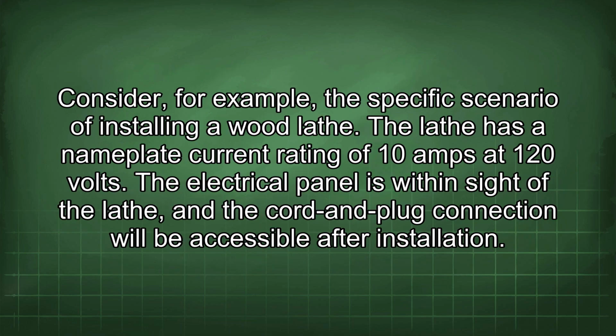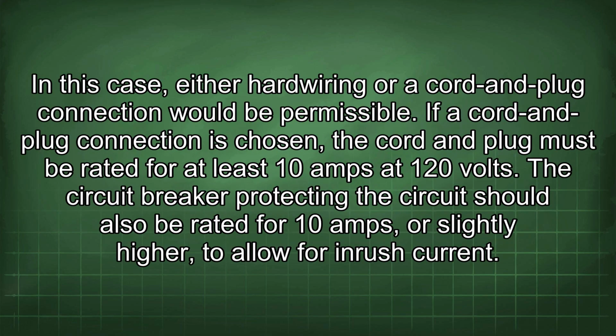Consider, for example, the specific scenario of installing a wood lathe. The lathe has a nameplate current rating of 10 amps at 120 volts. The electrical panel is within sight of the lathe, and the cord and plug connection will be accessible after installation. In this case, either hardwiring or cord and plug connection would be permissible.